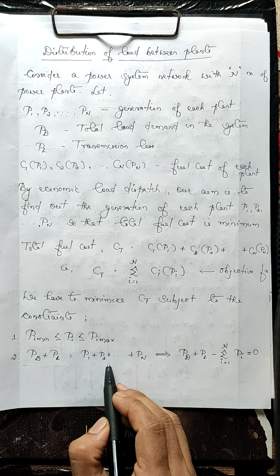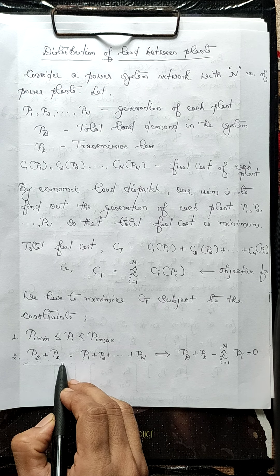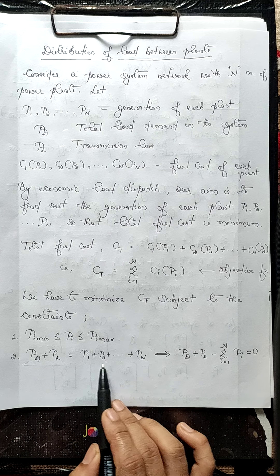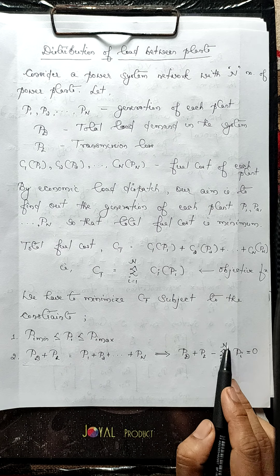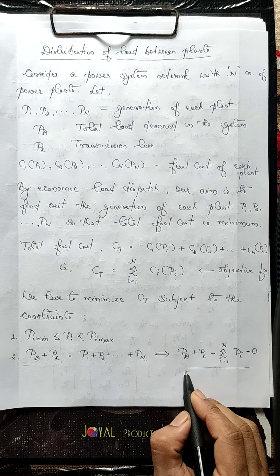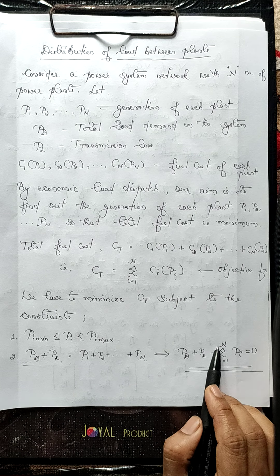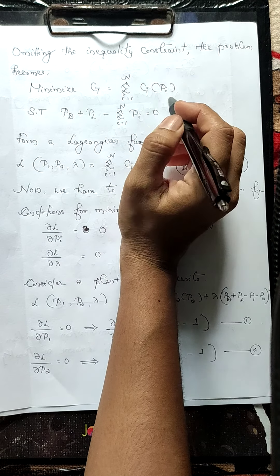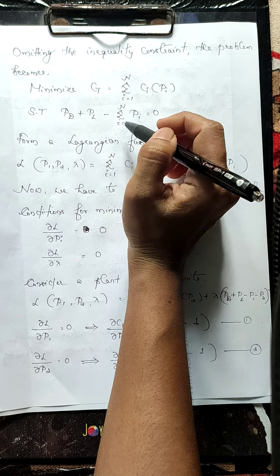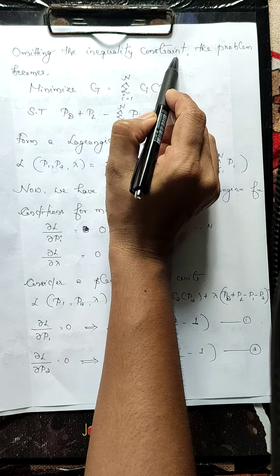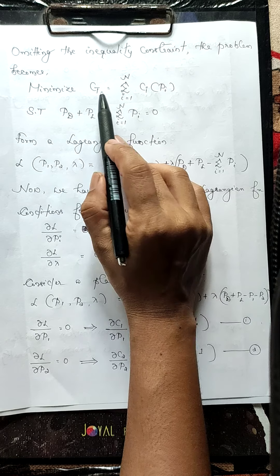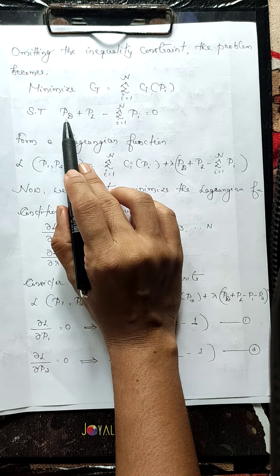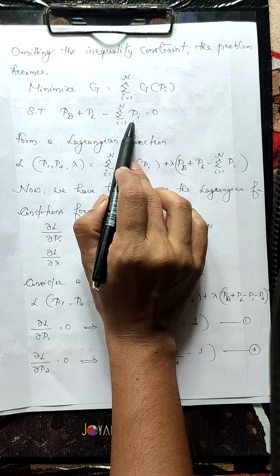So the total generation should equal total load demand plus total power loss: PD + PL - (P1 + P2 + ... + PN) = 0, which can be generalized as PD + PL - summation(Pi) for i = 1 to N = 0. For the time being we will consider only the equality constraint. Omitting the inequality constraint, our problem becomes: minimize CT = summation of Ci(Pi) subject to PD + PL - summation(Pi) = 0.